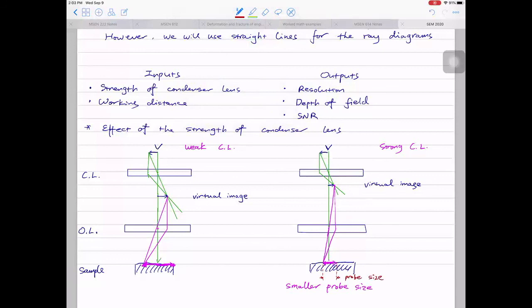We just learned something very important: one effective way to improve your resolution is to strengthen your condenser lens. If you have small features you want to resolve, you can strengthen the condenser lens to achieve better resolution.